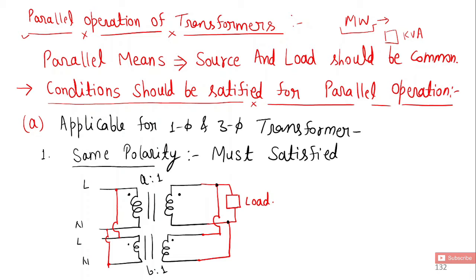Condition number one, applicable for single-phase and three-phase transformers: Same polarity. This condition must be satisfied. You can't connect without polarity, so all polarity at primary side you have to connect - line, neutral - and load side also you have to connect polarity points.